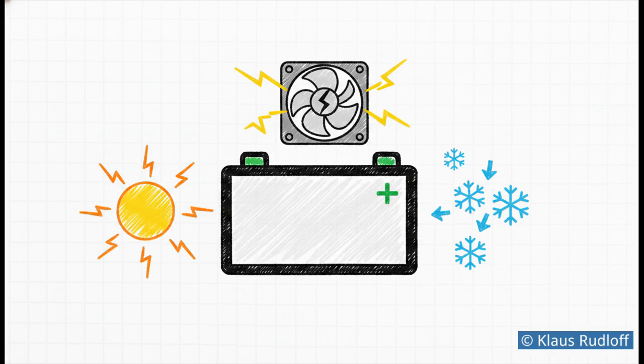Let's not forget cooling system maintenance. Keeping temperatures tightly regulated requires active mechanical cooling, usually liquid or some advanced HVAC system. But those cooling systems are mechanical assets themselves, and they become a massive point of failure if not rigorously maintained. If your cooling degrades, your battery degrades, and fans and pumps really don't care what your day 1 spec sheet says.